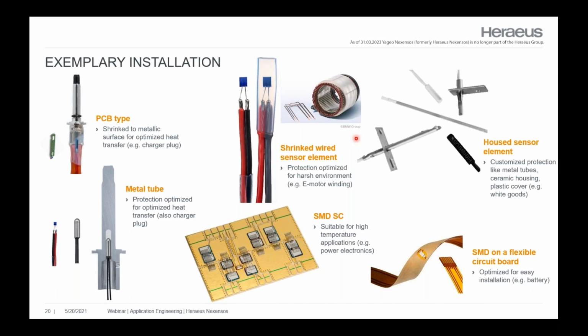What I want to show you as an exemplary installation in the end are these types which we saw before. We have here a PCB type, meaning an SMD mounted on a PCB, wired in the end. You see these red wires here, and then we put it directly on the backside of a connector for an e-charger, an e-mobility charger. Then you have an optimized heat transfer, because the sensor is very close to the heat source, since in that area the heat will increase because of connector resistance.